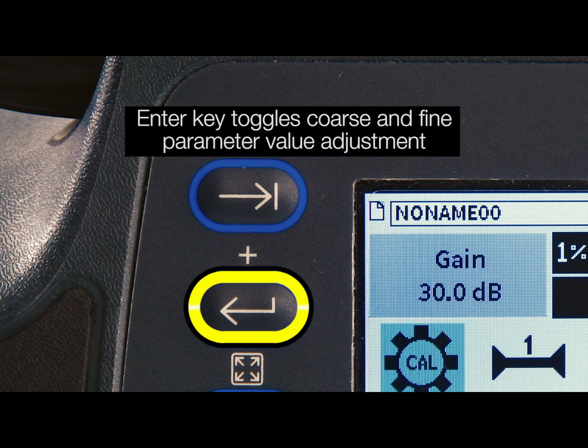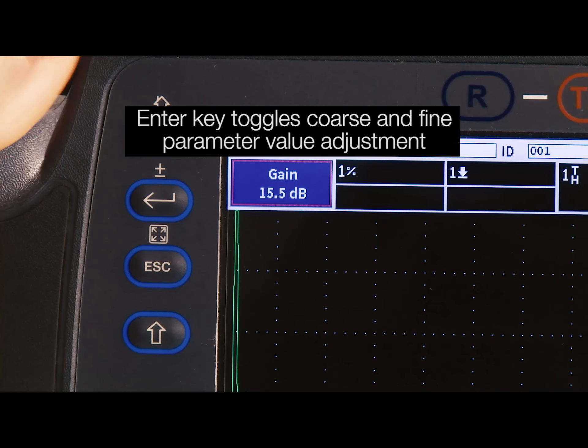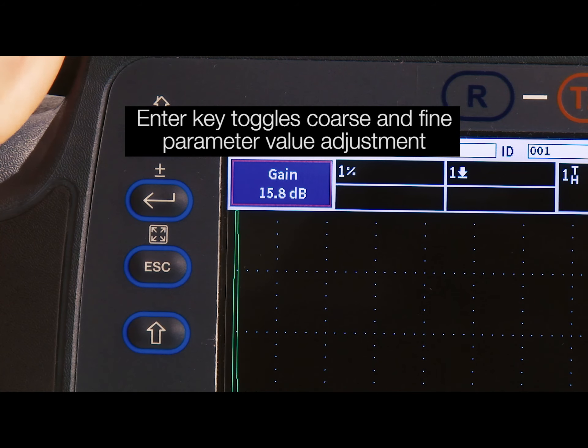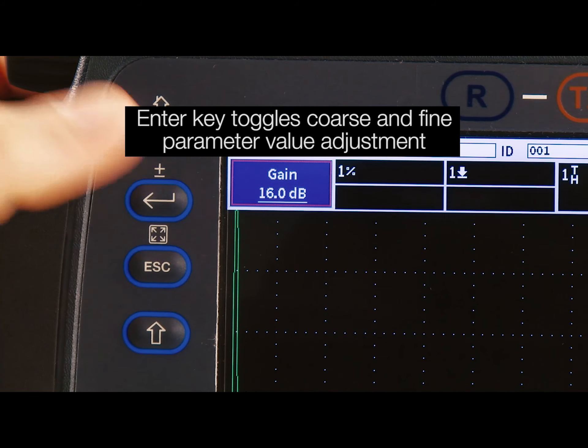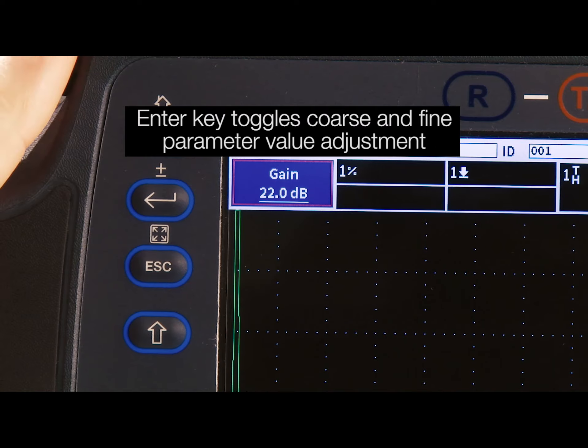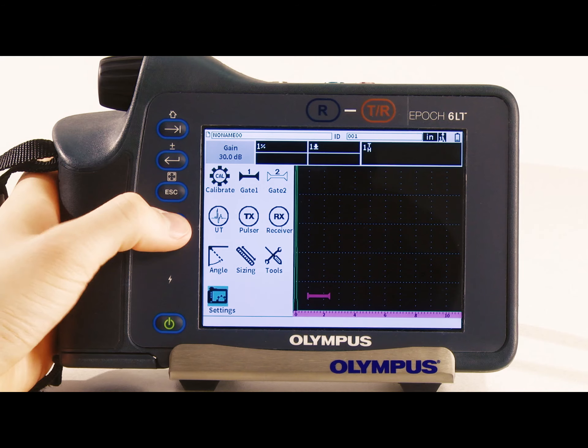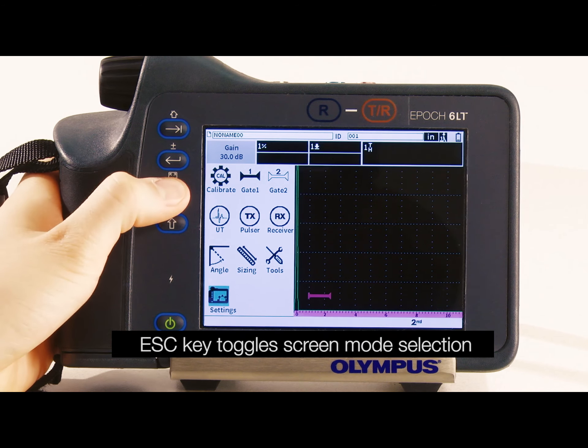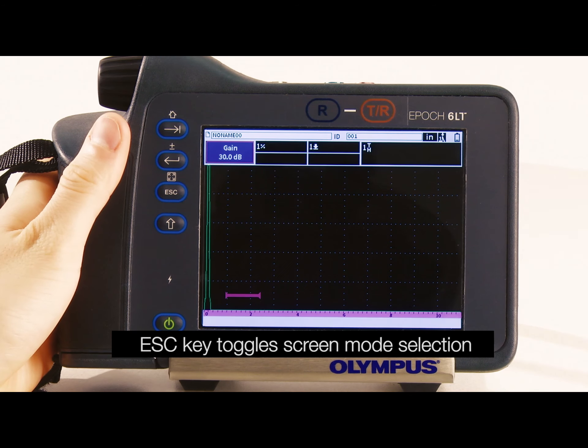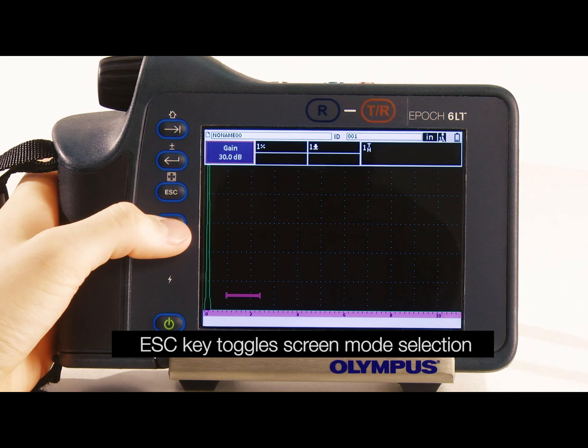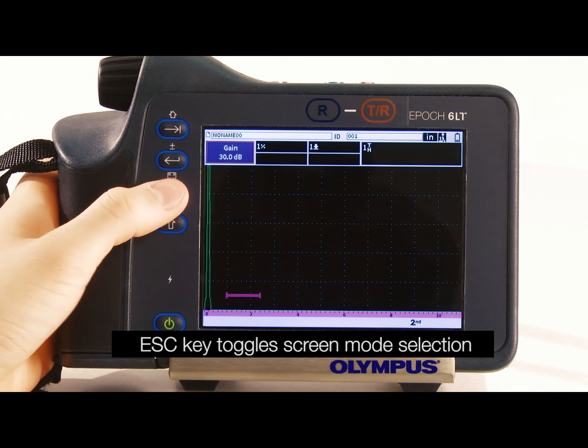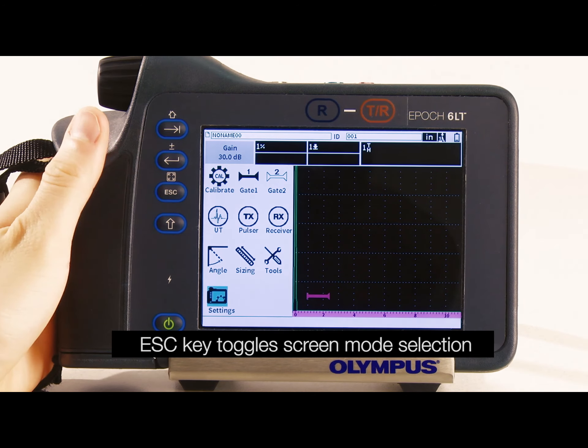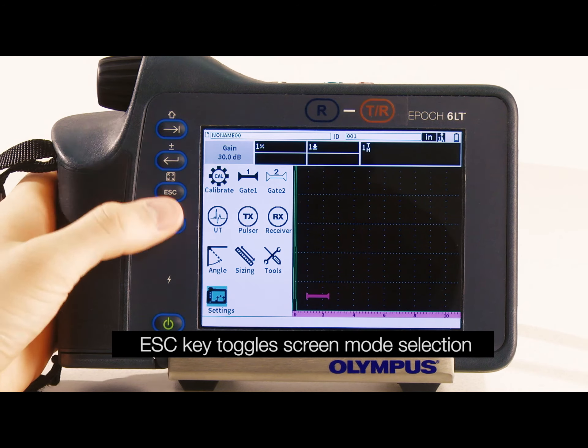The secondary function of the enter key toggles between coarse and fine adjustment of parameter values. Finally, the secondary function of the escape key toggles between the instrument's two screen modes: inspection mode and setup mode.